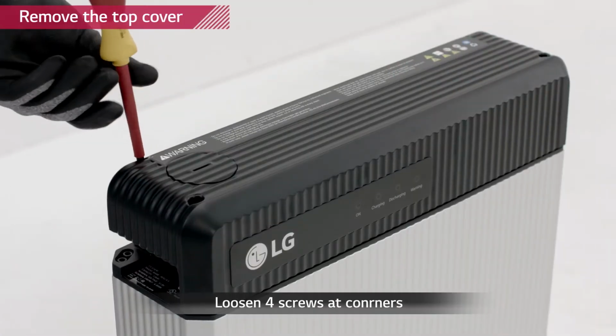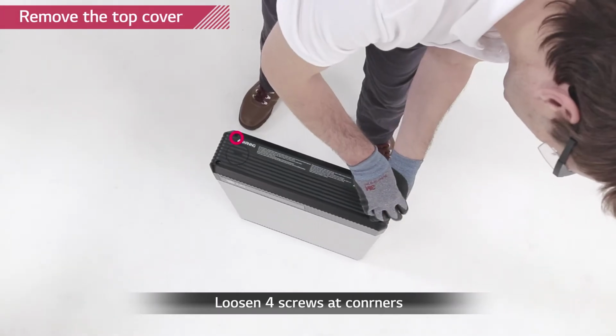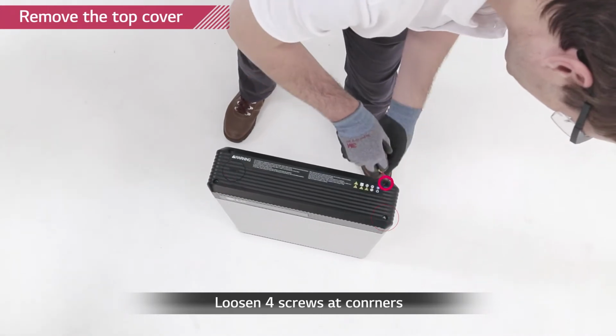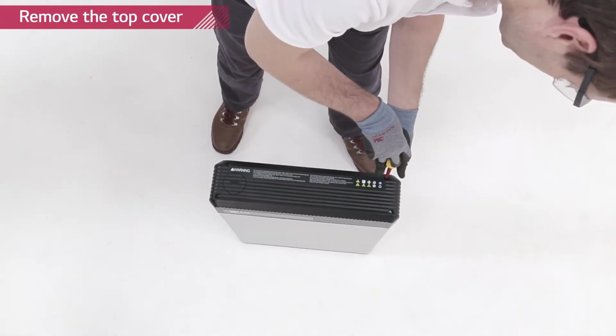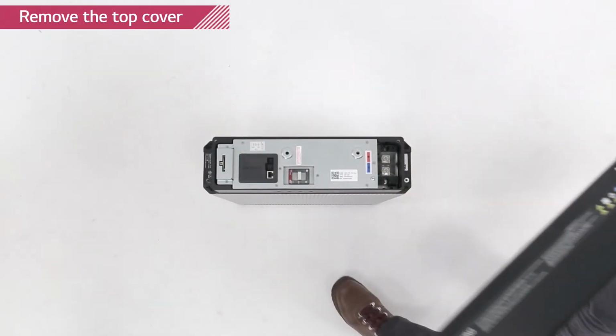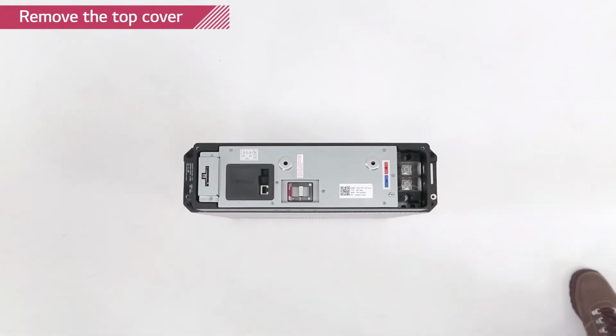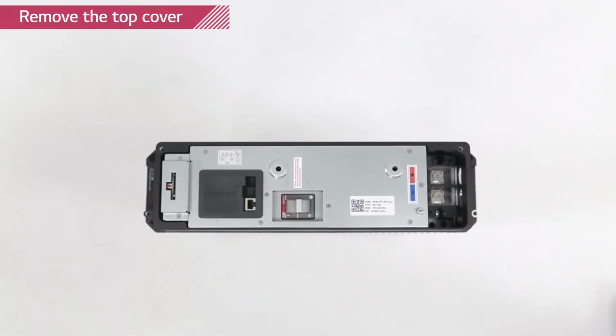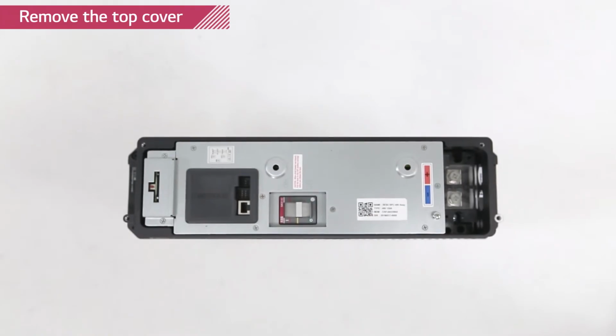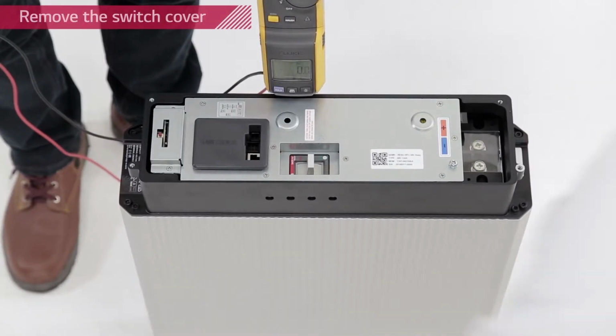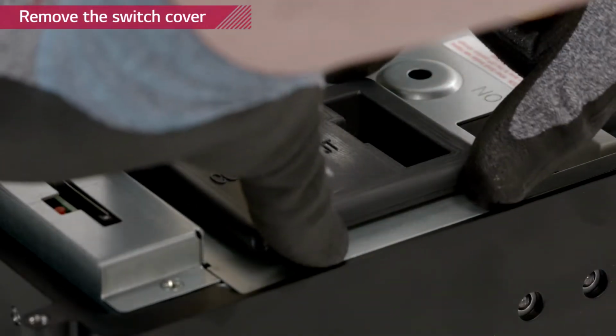Remove the top cover of the battery pack by loosening the 4 screws at each corner of the top cover. The circuit breaker should be in trip position. Now, we are going to set the rotary and dip switches in right positions so that the battery pack can communicate with its inverter. Remove the rubber switch cover by pulling it upwards.